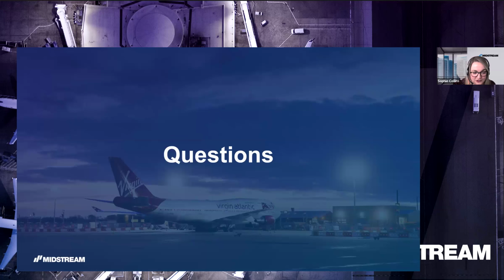First question: are the requirements from EASA for mobile lighting solutions the same as for normal stands, and do you help with calculating the optimal placement and height? Yeah, I think we did cover it - EASA and ICAO don't in any way have a different approach for the types of lighting. The requirements are fixed and well known: you have to have average light levels of 20 lux or above, with a uniformity ratio of 4:1 or better, and a glare rating typically of 50 and below.